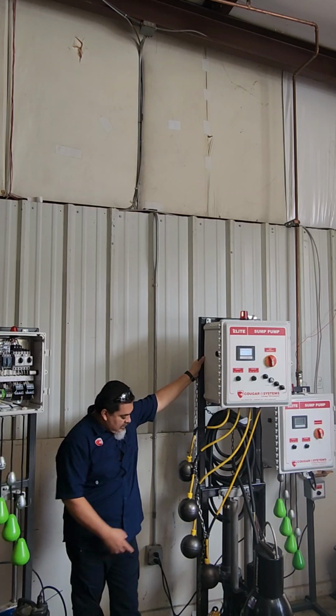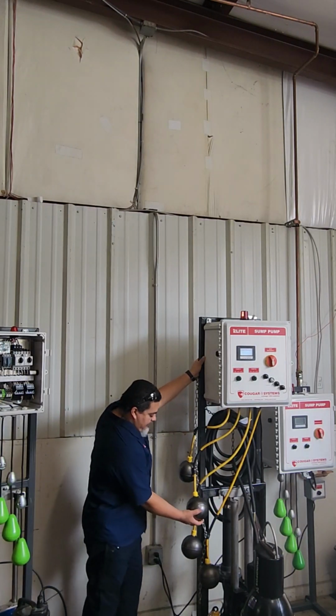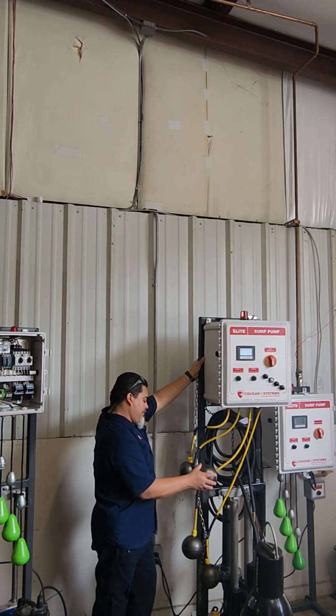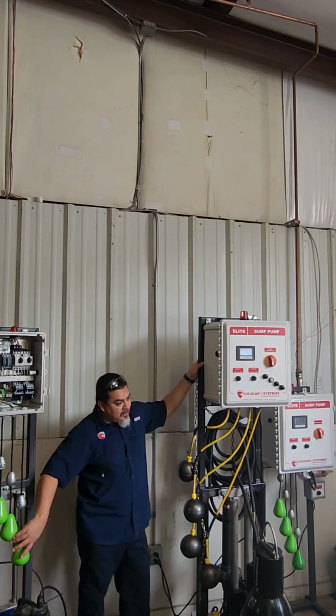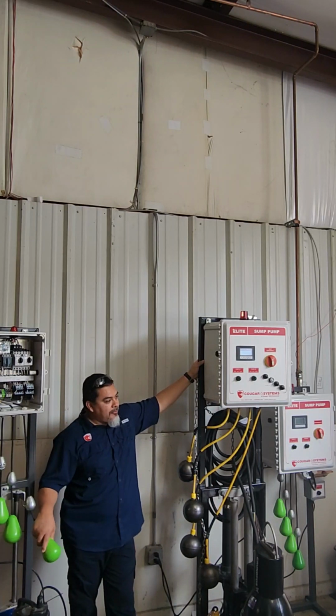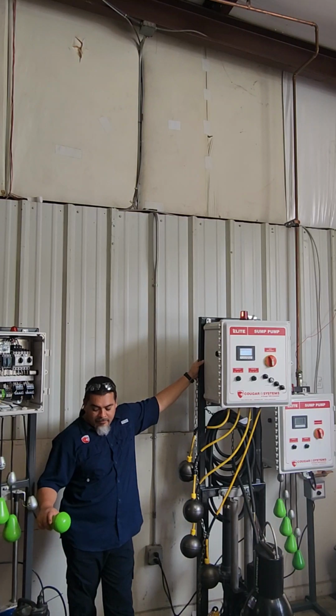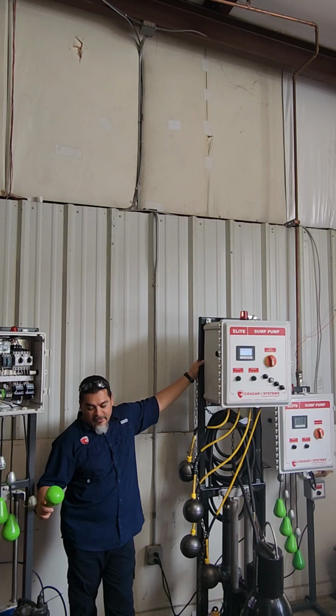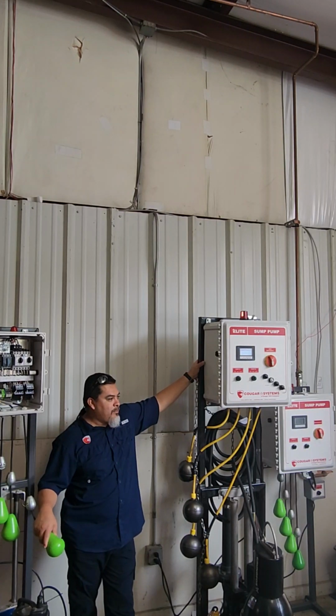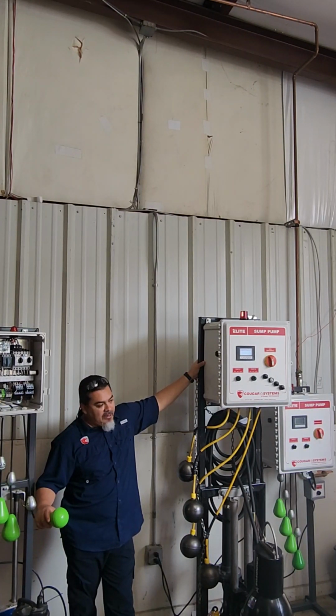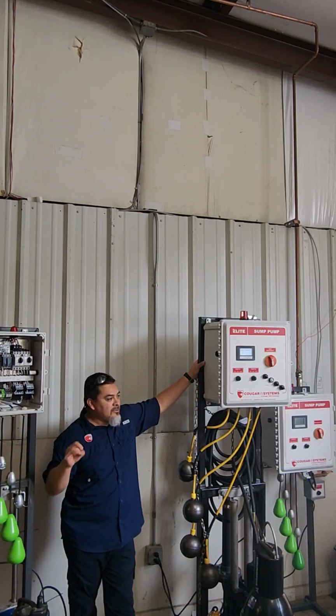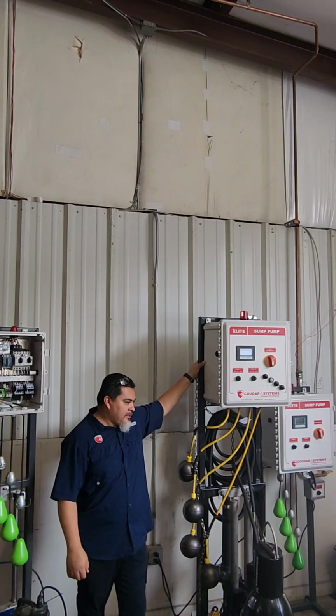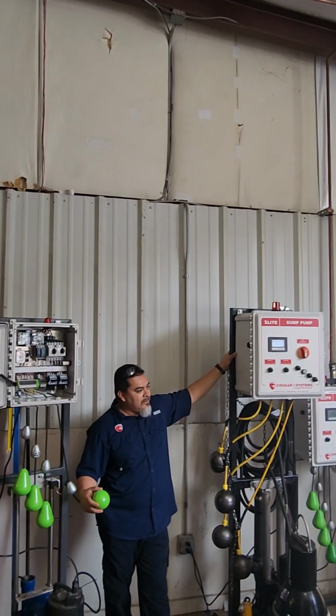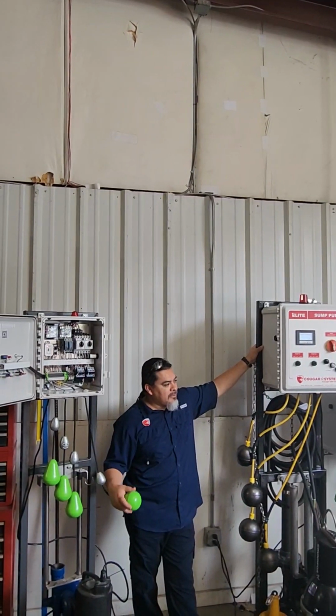Because for example, these are mercury. I don't know if you've ever seen the yellow floats. Yeah. Okay, those are mercury. So those are narrow angles. The float just has to barely tilt and it activates, compared to the 45. So there will be a time delay on that, because if not, a wave, bam, starts chattering and causes your contactors to burn out. So I always recommend getting away from the yellow ones and going with the green ones because of the angle.